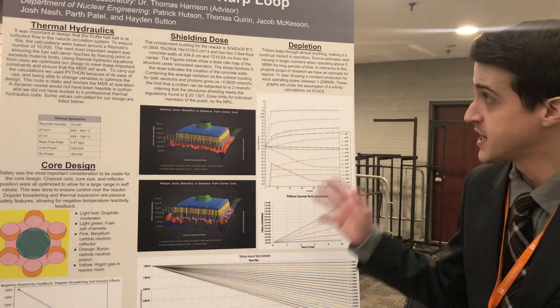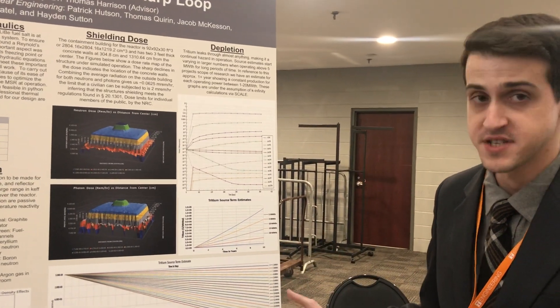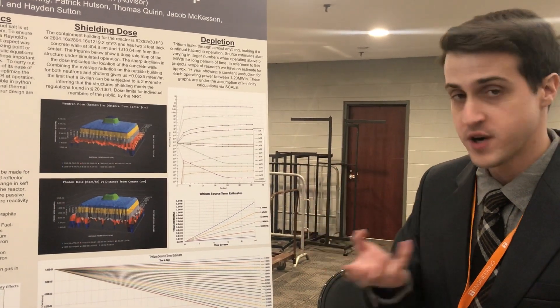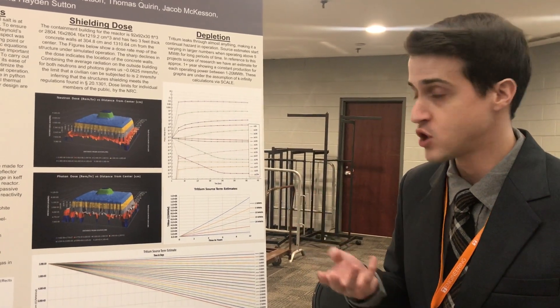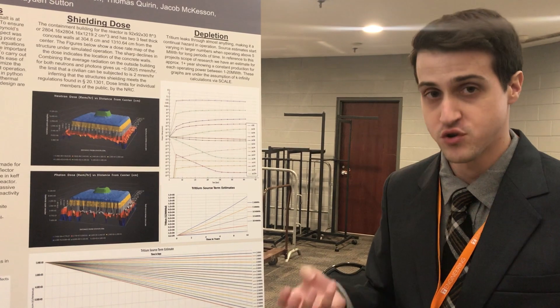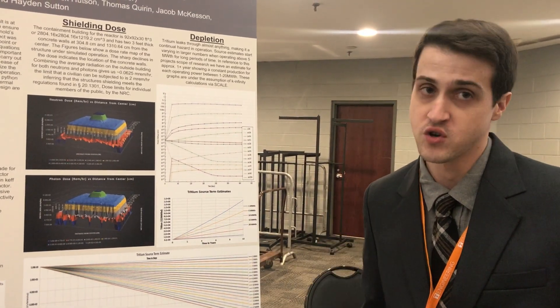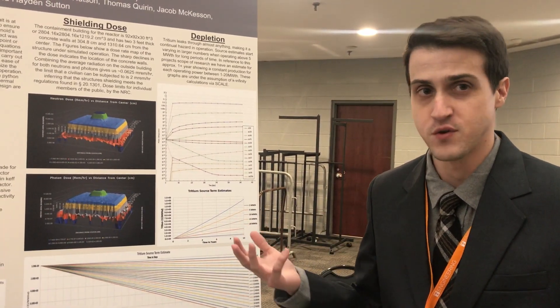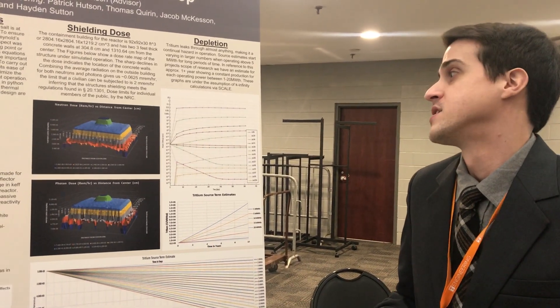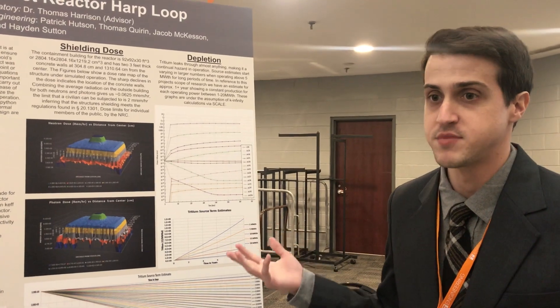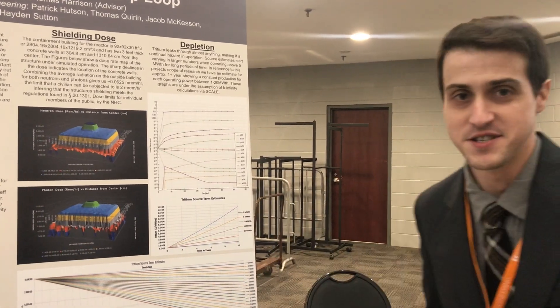A big aspect of this design is passive safety. The core has a melt plug: if the salts going to the core get too hot — above 900 degrees Celsius — that plug will melt and drain the core. So a meltdown is virtually impossible with this design. This design concept has been known about since 1950, and we're hoping it catches on.